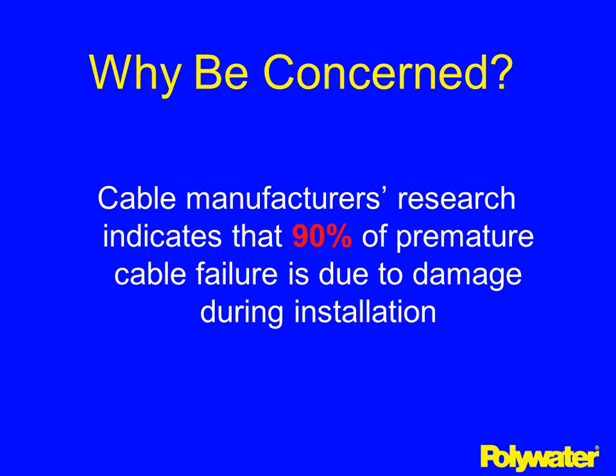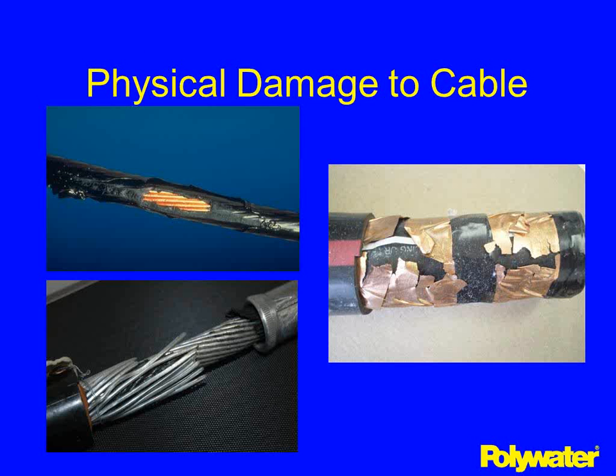You should care because replacement of failed cables costs millions of dollars per year. Installation is the most significant contributor to failure. Most cable damage is not visible to the installer or the customer. Failures usually happen weeks or months later and will reduce the overall life of the cables. Manufacturers have discovered that over 90% of premature failure is due to damage during installation.